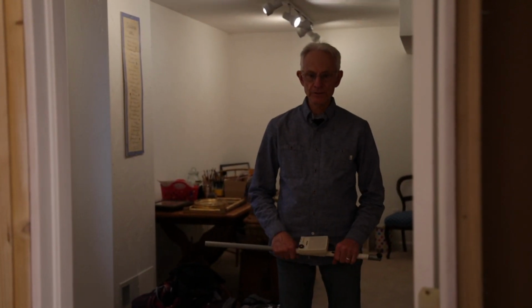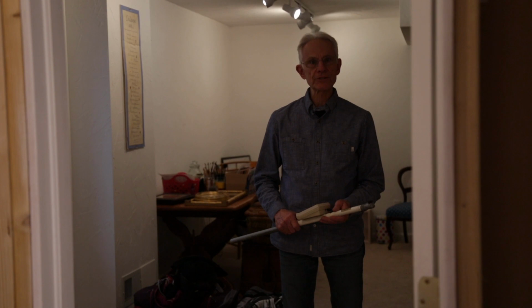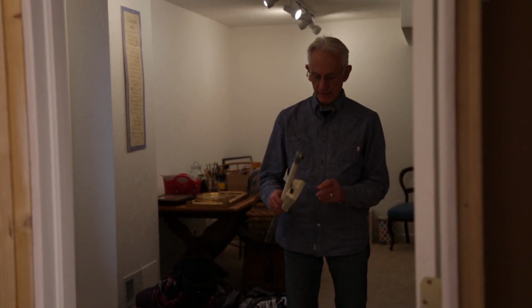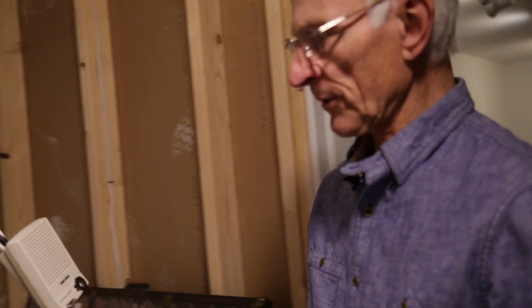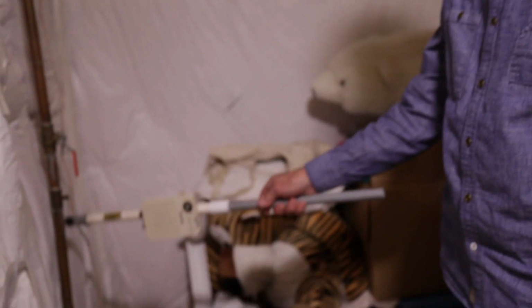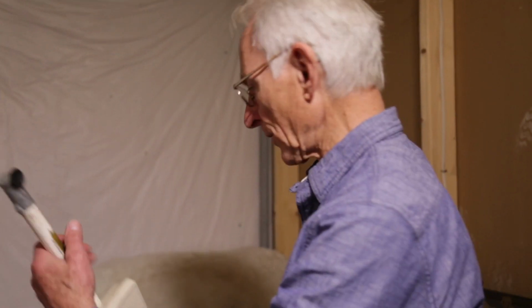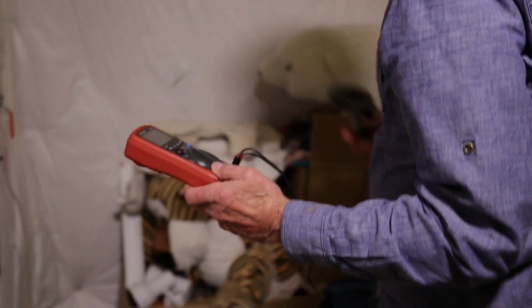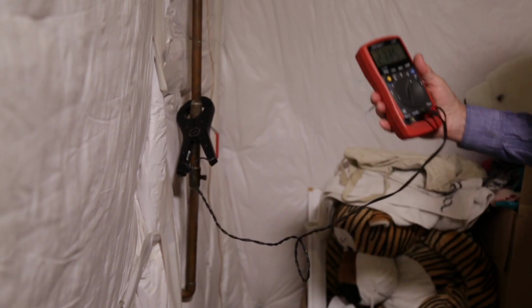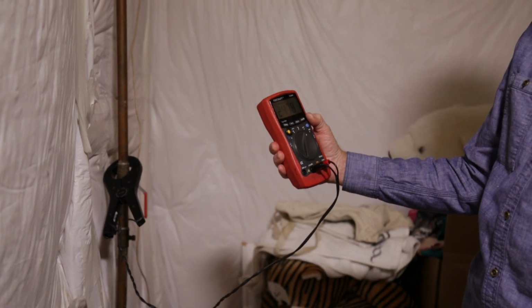I've come down to the basement to investigate the water entrance to the house to see if there's current flow on the water pipe. I brought along my trusty buzz stick to be able to check that really quickly. So we go over here to the water line and give it a check. There's plenty of current and buzzing associated with that. Let's just give it a check now with our clamp-on ammeter to see how much current is on the water pipe. At the present time, we've got like 24 milliamps flow.